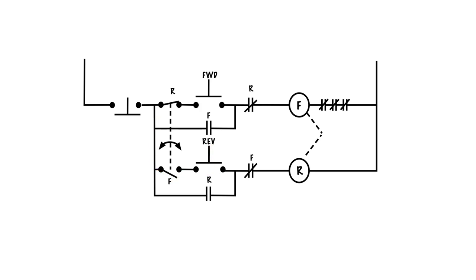The power can't get through until the motor itself has stopped spinning and this zero speed switch has closed. So it's locking it out until the motor stops. I let go of the stop button, it bounces back to its normally closed position, and again as long as this motor is spinning in the forward direction through inertia I can hit this as often as I want, R will not energize because it's being held out.